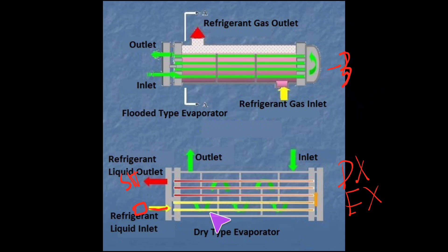Whereas when you start stepping into DX design, vast majority of the time I will see these anywhere from maybe four at the really low end if it's doing really well or if it's a newer system, all the way up to about 10 degrees of approach. When I'm working on these and I start seeing more than 10 degrees, I start getting really concerned because something's just not right there. Something's not transferring properly. The actual most common field use of this is usually between six to eight degrees. Six is probably the most common that I run into.